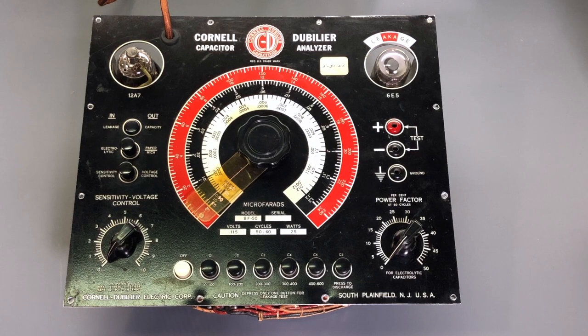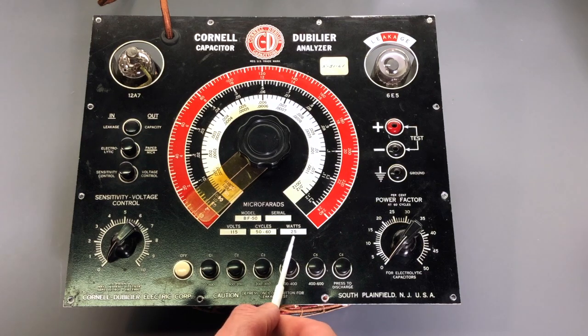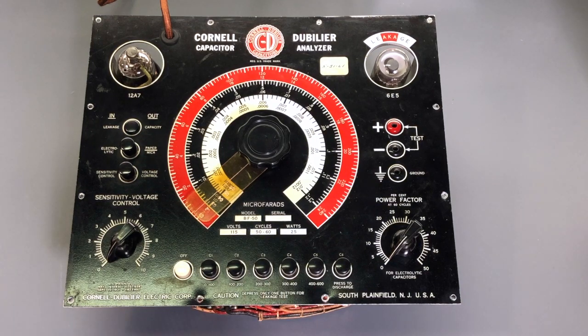that was in series for current limiting with a 1/4 amp fuse. The 1/4 amp fuse at 120 volts provides 30 watts. The tester is rated 115 volts at 25 watts. So the fuse will provide the safety that we need should there be a short circuit or an overload inside the tester. That fuse would go away.